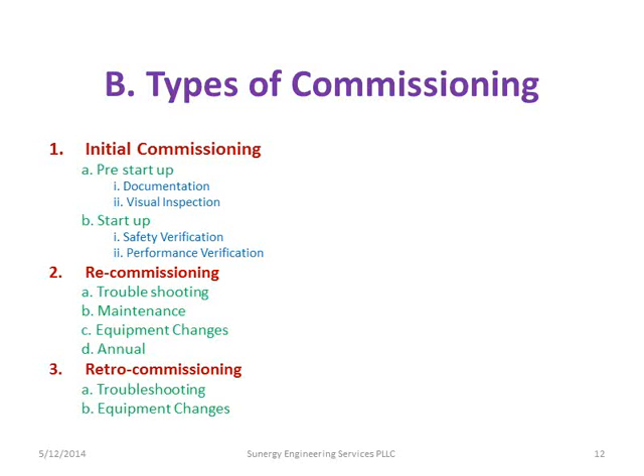Then we have what we call recommissioning, which happens on an annual basis, or comes up because you've got some troubleshooting to do, something that's wrong, a performance issue you're trying to track down. It's already been commissioned once, so you're just going back and doing an annual maintenance checkup, or going back to track down a problem.